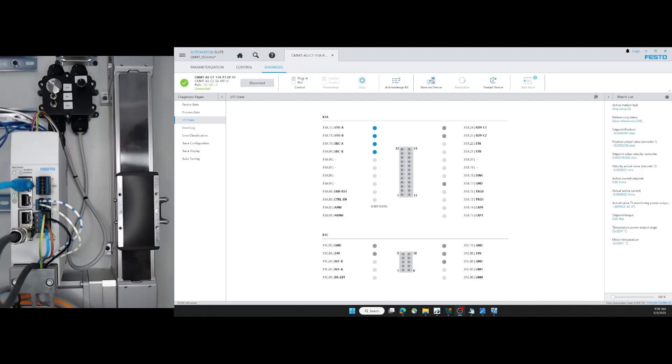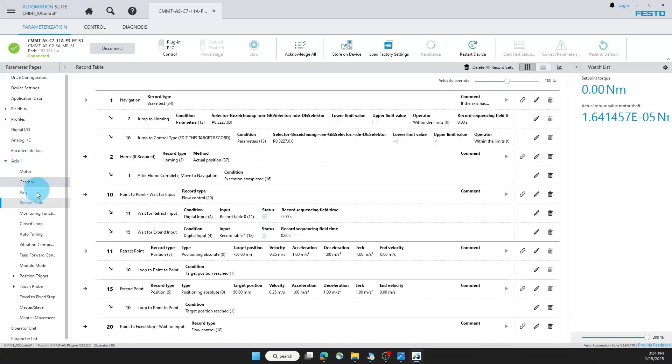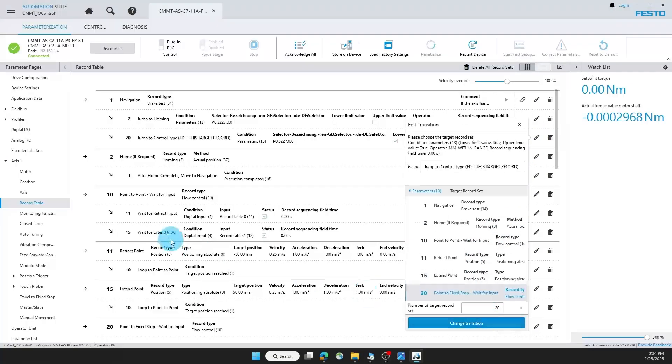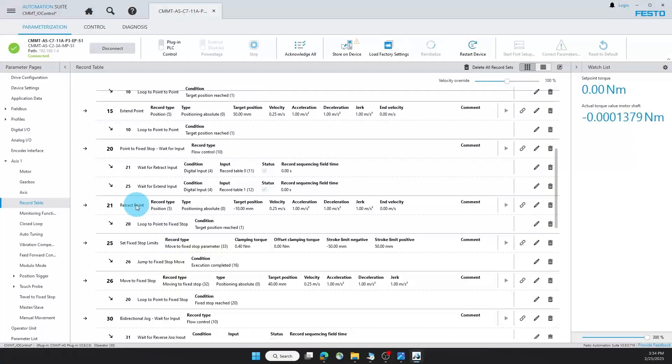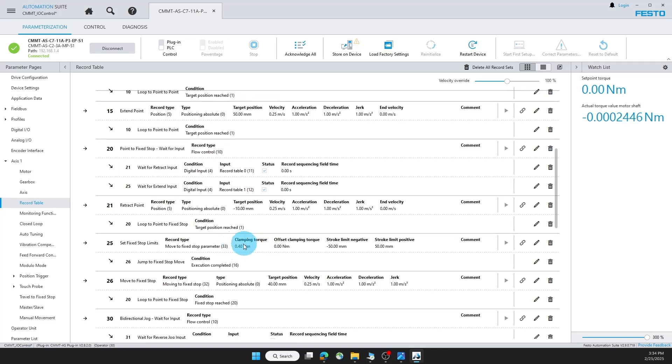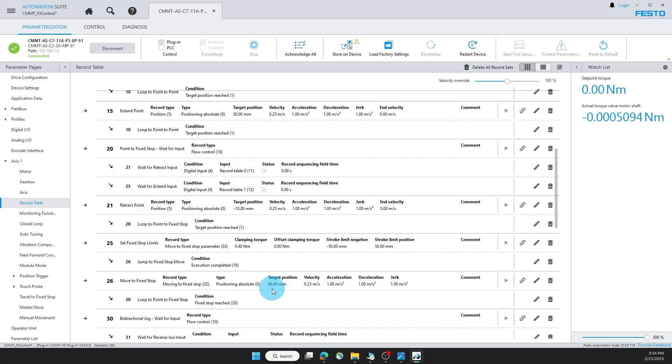Now let's take a look at point to fixed stop. Back to the record table. In record one I can change the transition to 20. In this section, you'll notice a retract point same as last time, but now I have two different records. I have a fixed stop parameter and a fixed stop move. In the parameter, I can define the maximum torque that the axis will output before considering move complete. So this can be used for holding position. In the move, I can define target position, which will be the maximum position that the axis will move to before searching for the torque being exerted.